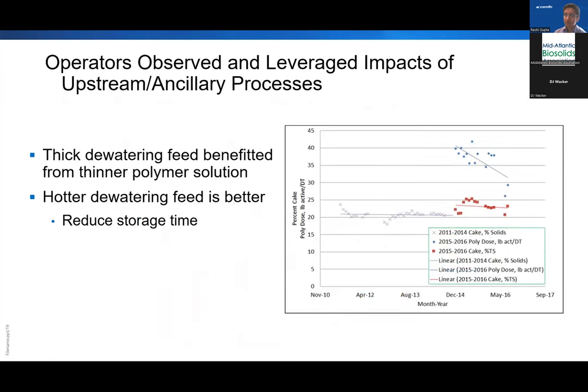The operators also observed and leveraged the impacts of the upstream processes and some of the ancillary processes. So they found that when they had thicker digested sludge coming in from their sludge storage tank, the system worked better when they thinned out the polymer solution. So they reduced the concentration of the polymer that they were using, and they found improvements.